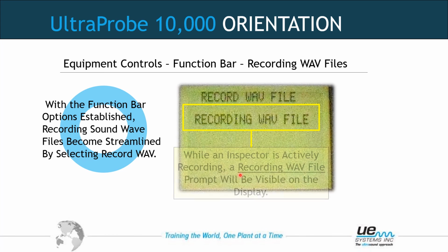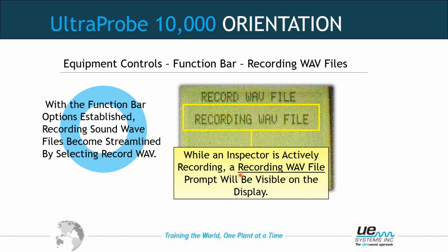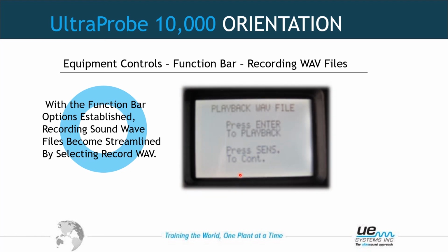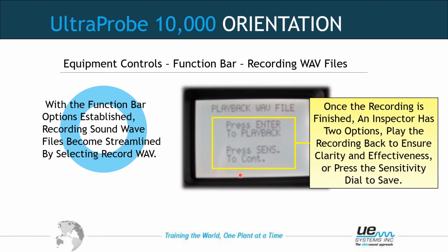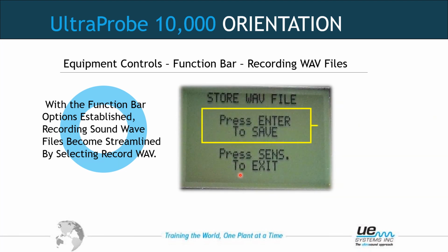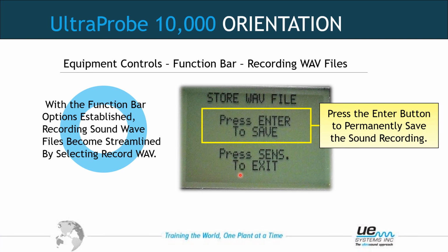As it's recording, you'll see recording wave file. When you release it, or if it was in a preset time and the recording is over, you will see the next screen. Press enter to play back, press sensitivity to continue on storing. You could play it back and listen to make sure you got a good recording. If you like it, continue on. Either way, you have to press sensitivity to continue. Your next screen gives you 2 options. You liked it, you want to save it, or you press sensitivity to exit out and start again.